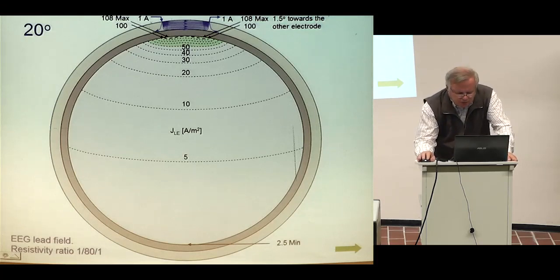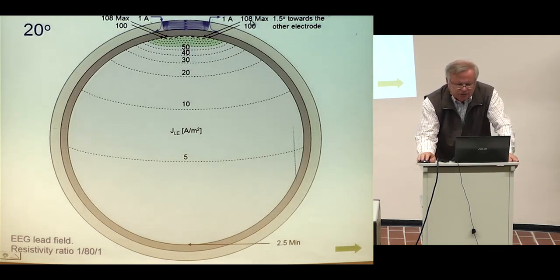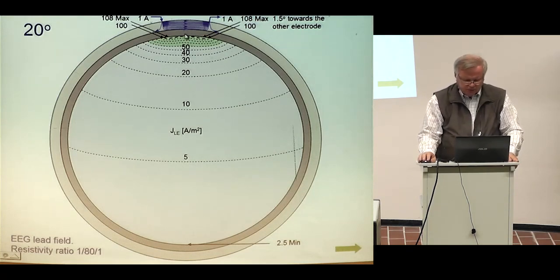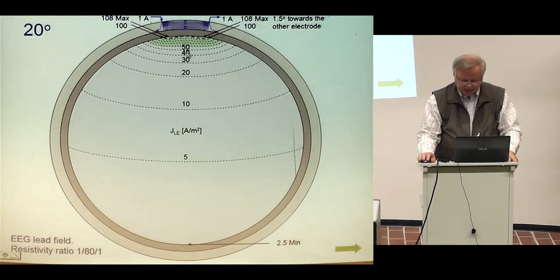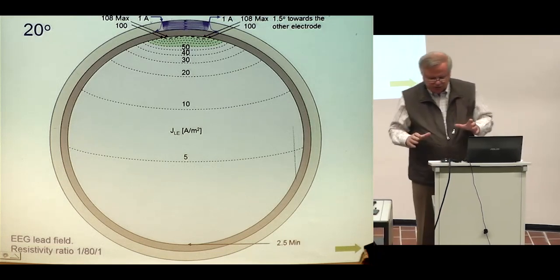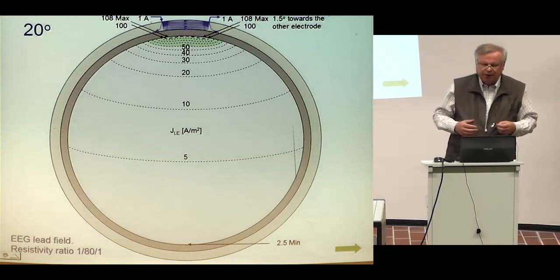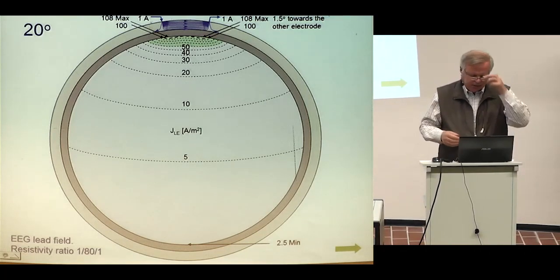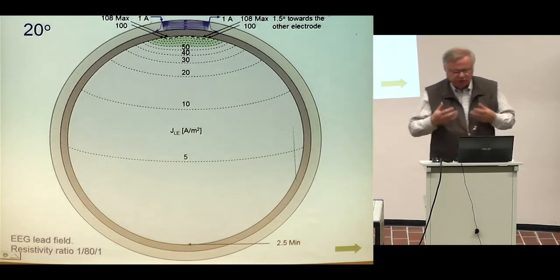In the close-electrode case, you see clearly how the measurement sensitivity is very low on the opposite side — 2.5 — while the maximum is 108. So it is 40 times higher under the electrodes, which means that with this kind of bipolar measurement, you get practically no signal anywhere else than just from under the electrodes. The basic calculation was made by Rush and Driscoll, and we recalculated the results, added the isosensitivity surfaces, and created the concept of the half sensitivity volume.